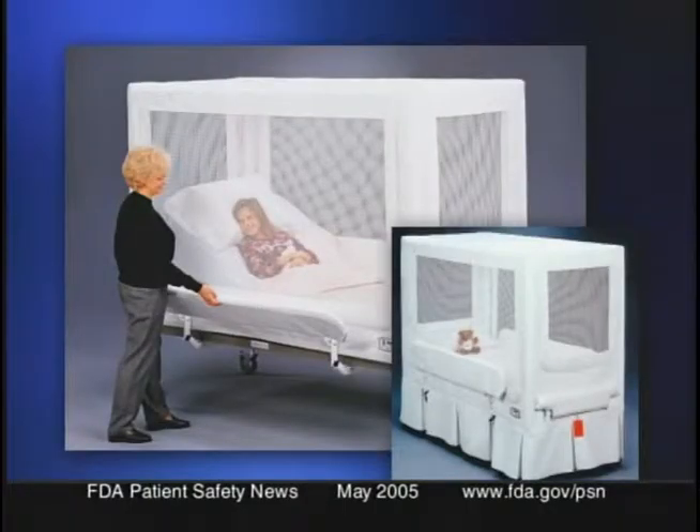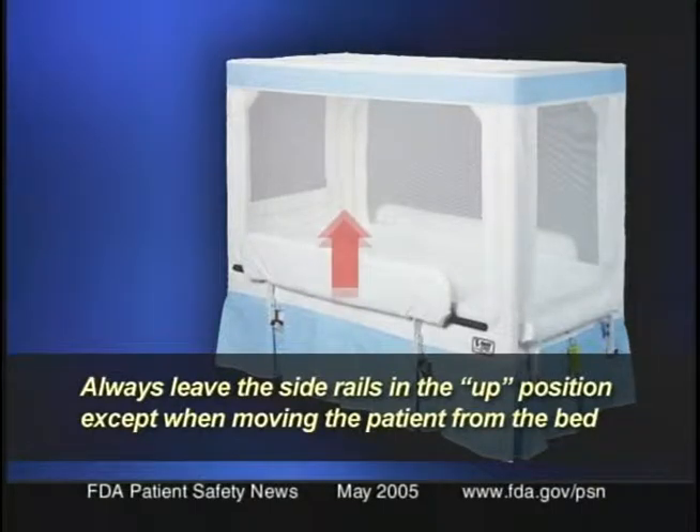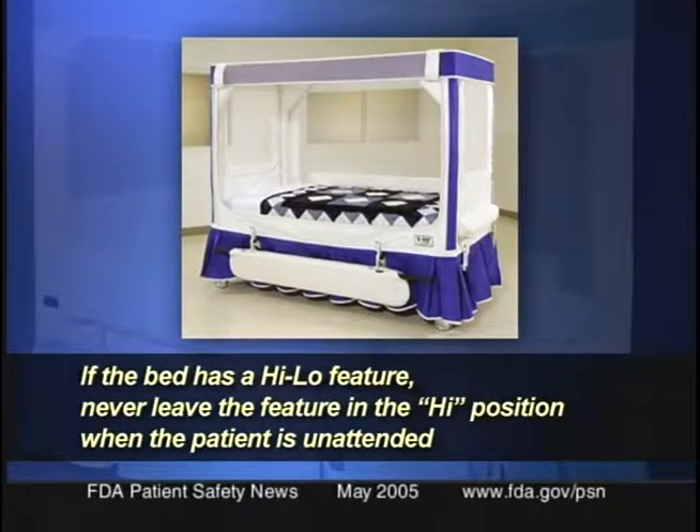More than half of these events involve children aged 16 and under. FDA recommends that hospitals, nursing homes, and consumers who have a Vail enclosed bed system stop using it immediately and move the patient to an alternate bed. If the only option is to continue using the Vail bed, FDA recommends following these safety precautions: use only the mattress recommended by the company; always leave the side rails in the up position except when moving the patient; and if the bed has a high-low feature, never leave it in the high position when the patient is unattended, because the patient can become entrapped. Check our website for additional information and updates as they become available.